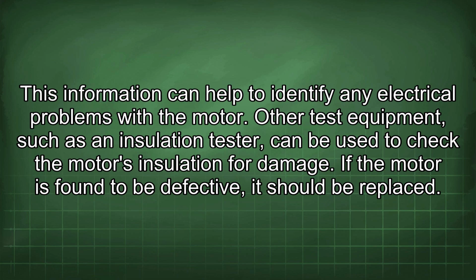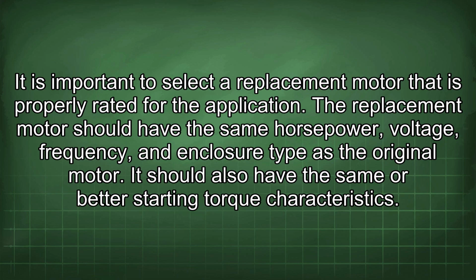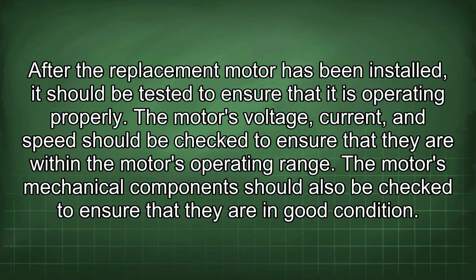Other test equipment, such as an insulation tester, can be used to check the motor's insulation for damage. If the motor is found to be defective, it should be replaced. It is important to select a replacement motor that is properly rated for the application. The replacement motor should have the same horsepower, voltage, frequency, and enclosure type as the original motor. It should also have the same or better starting torque characteristics. After the replacement motor has been installed, it should be tested to ensure that it is operating properly. The motor's voltage, current, and speed should be checked to ensure that they are within the motor's operating range. The motor's mechanical components should also be checked to ensure that they are in good condition.